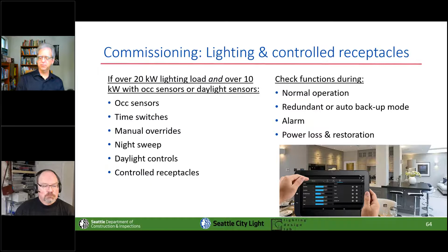Shaun, on commissioning: just a quick note here. The lighting industry has long been guilty of imprecise language. When we talk about starting up a lighting control system, and I'm as guilty as anyone, we've long talked about commissioning the system, as in programming it. But this is not what commissioning is. Commissioning is a third-party verification process. Those of you in the HVAC world are long familiar with the notion of commissioning, but in lighting, not so much. IES has DG 2911, the design guide for commissioning process applied to lighting control systems, a fantastic document that gives you a step-by-step flow chart of how and why you commission these things. But they are not the same as programming.